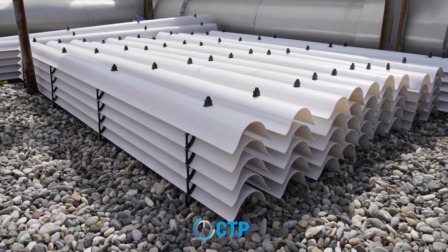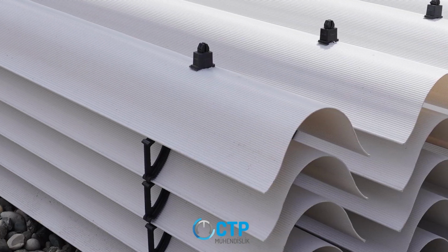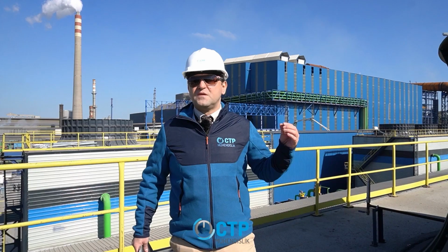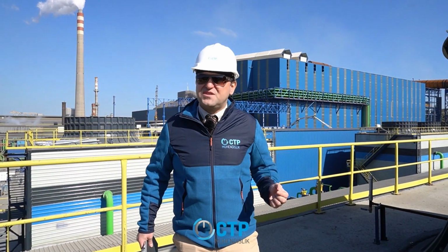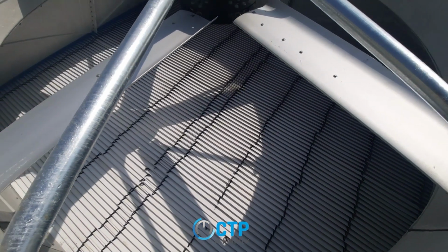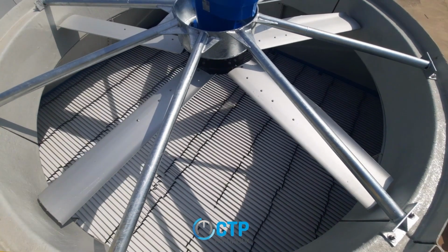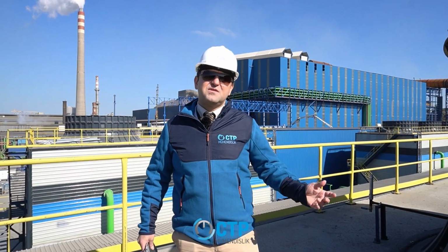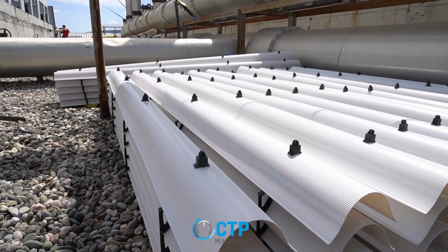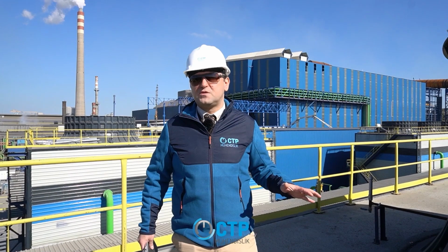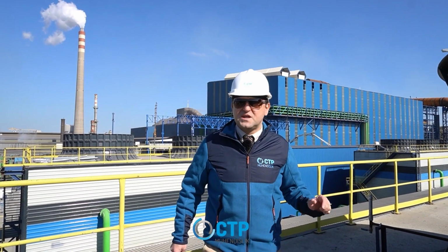Droplet separators guide moisture-laden air through specially designed bends called passes. This process causes tiny water droplets in the air to impact the vane surfaces. On these surfaces, the small droplets combine to form larger drops of water, which then drip back down into the system, effectively reducing water loss. Droplet separators may seem like they don't serve much of a purpose, but they are actually materials that enable the recovery of a significant amount of water.